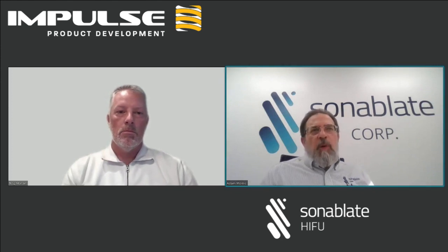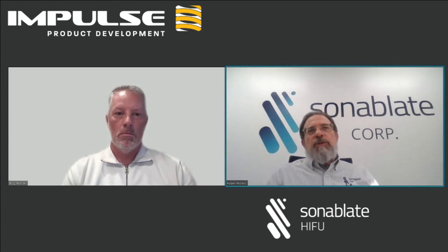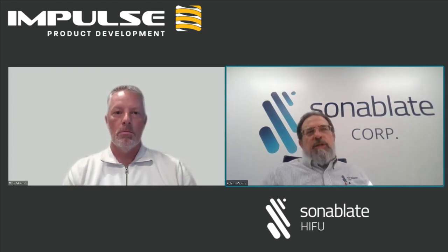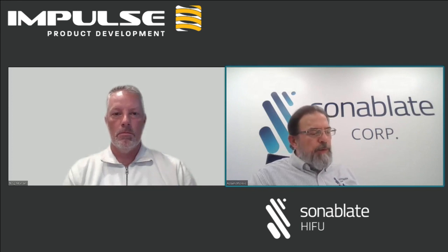One of the caveats with our system is the probe tip, what we call the probe tip, where the ultrasonic transducer has a circulating water bath around it. So it's dressed with a sheath, sealed, and then there's cooled, degassed water circulating. Those water lines run through the probe housing and into what we call the probe tip, the distal end of that probe where the transducer is.